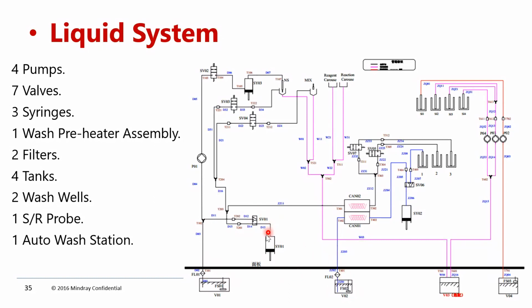This is syringe 01. When SV01 turns on, this syringe will pull the liquid from the tank. This syringe is filled with water. When you do the first-time priming, it will remove all the bubbles. After that, the instrument always has water inside syringe 01. Syringe 01 is connected to the preheater assembly, from the preheater to the wash station dispensing lines, and it is responsible for the external wash of the sample and reagent probe and mixer washing. So syringe 01 is responsible for cuvette dispensing washing as well as the external wash of the sample probe and mixer unit.